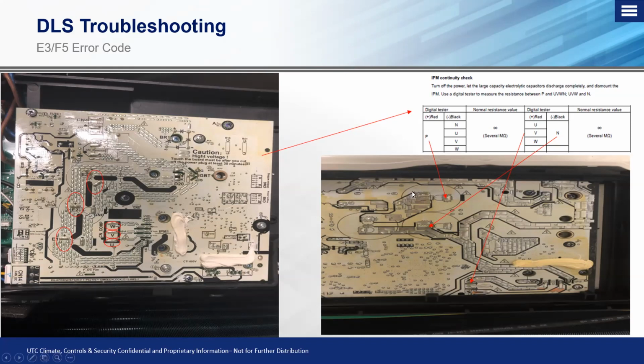You just got to be more mindful at actually looking at the physical layout or the printed circuitry of the board and seeing where those capacitor buses are and where your compressor or your outdoor fan motor hooks up to the board, so you can test on the appropriate terminals. Okay, but if you have the split type board, you want to reference this one on the left. If you have a single board, this is what you want to reference on your right. And this is how we can get through it again and make sure that the IPM board actually is working electrically and also working properly.